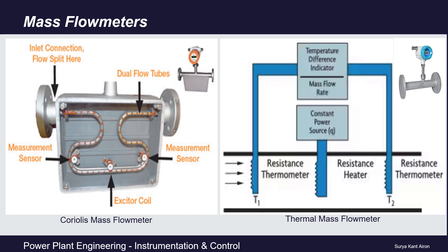Thermal mass flow meters employ the thermal dispersion principle, whereby the rate of heat absorbed by a fluid flowing in a pipe or duct is directly proportional to its mass flow. One temperature sensor is installed upstream of the heater and another downstream. The temperature difference — delta T — across the heater indicates the heat absorbed by the fluid, which in turn gives the mass flow indication.